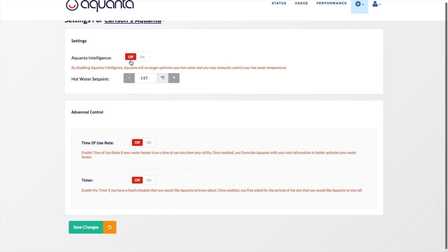A couple of caveats to note in this feature. First, Aquanta cannot heat a tank to a higher temperature than its nominal thermostat setting. Aquanta controls tank heating by allowing or disallowing power to flow to the heating element or ignition control, not by directly controlling a tank's thermostat. Second, Aquanta measures the tank's temperature via an external sensor at or near the top of the tank, so when in manual temperature control mode, it will turn off the tank's heating element when it reaches the set temperature as measured at that tank location, meaning that the rest of the tank may or may not be heated to that temperature. This is opposed to normal tank operation, as the water heater's mechanical thermostat measures temperature at the bottom of the tank. Aquanta's automated hot water available threshold does come into play here, as it will activate once it drops below a certain threshold to ensure that more than just the top layer of the tank is heated.